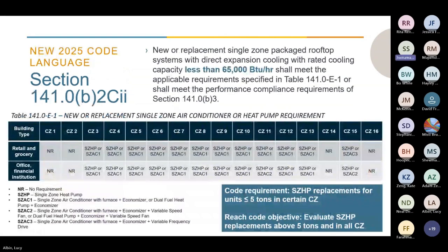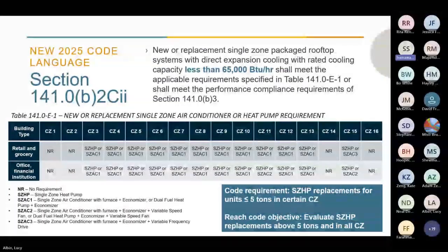This is an overview of the new 2025 code language, which serves as the primary catalyst for our study. The new code requires that all single-zone package rooftop units with cooling capacity less than 65,000 Btu per hour, equivalent to about 5 tons, get replaced by single-zone heat pump units in select climate zones shown in the table. It mostly applies to climate zones 3 to 13 and 15.